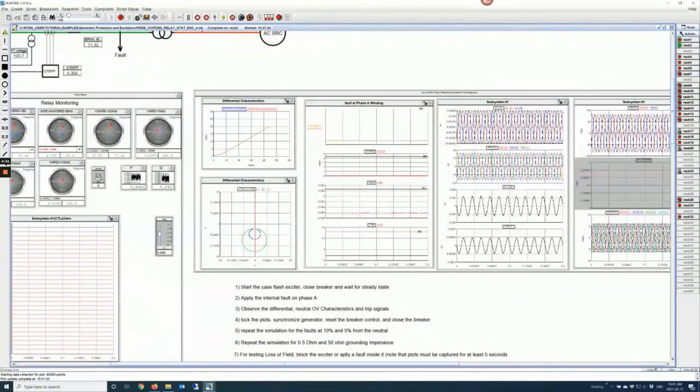Here we have terminal voltages and machine current, the stator currents. See, this is a faulted machine model. iMac A1 and A2 are stator currents for phase A, but for portions A1 and A2 of the sub-windings. Right now, because there is no fault, they're identical.